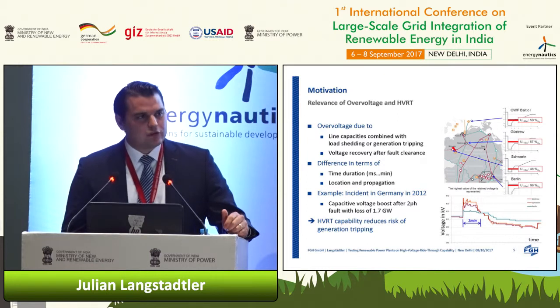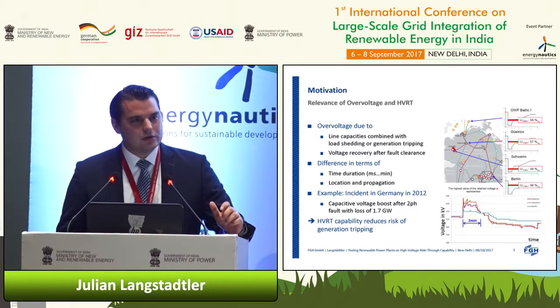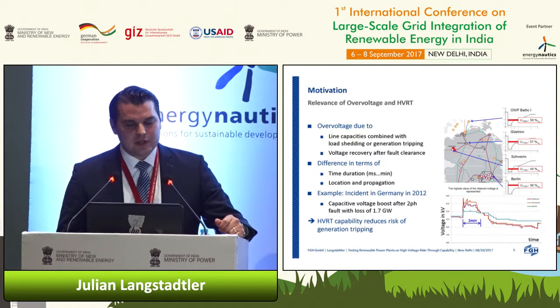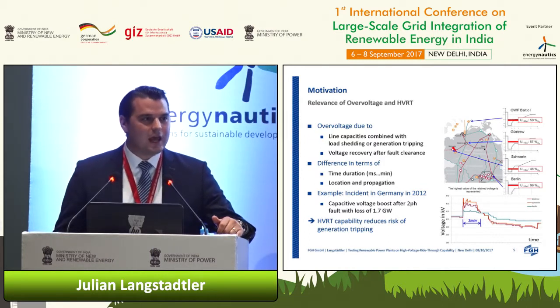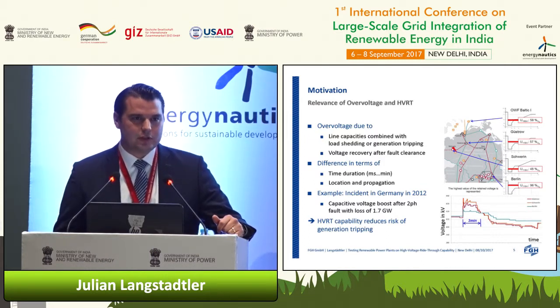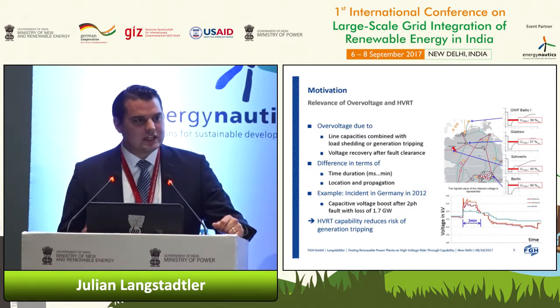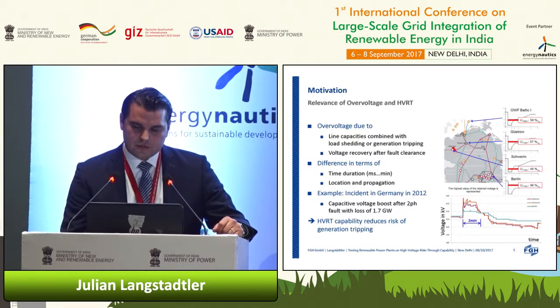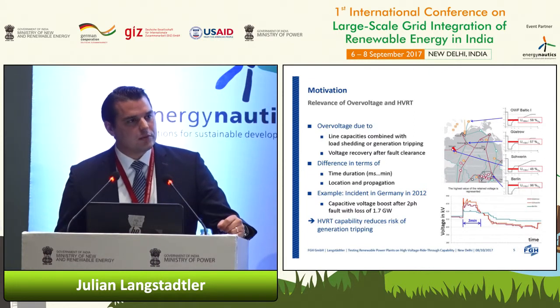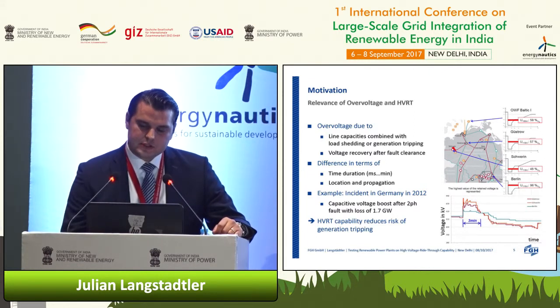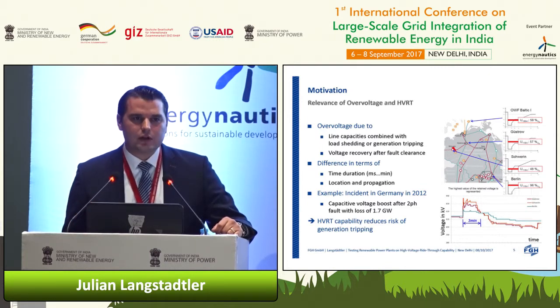And whenever I talk about LVRT, I always show a scenario which was calculated in Germany in 2001, which actually happened also in 2006 with a major incident. And we also had an incident, a major one in Germany in 2012 in the grid of the system operator 50 Hertz, which was also introduced on Wednesday. That is more or less a system which is in the northeastern part of Germany, which is characterized by high penetration of renewables, whereas the load is very small, comparable.